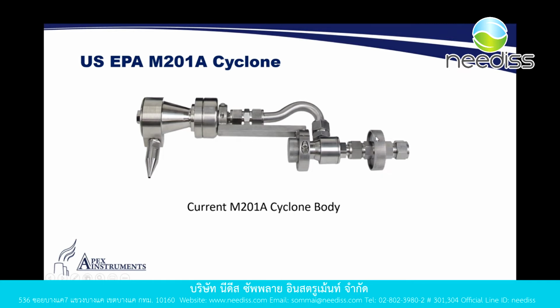And as I mentioned before in the picture, this is our filter. It's a 47 millimeter glass fiber filter, provided the temperature is okay for glass fiber. If not, it may be Teflon, but it's a 47 millimeter size filter here at the back to do that final capture of the particulate in this method.